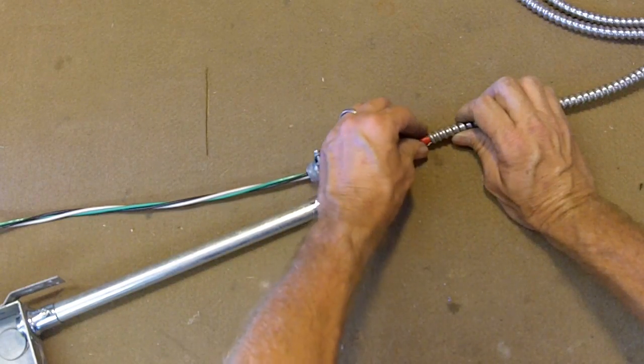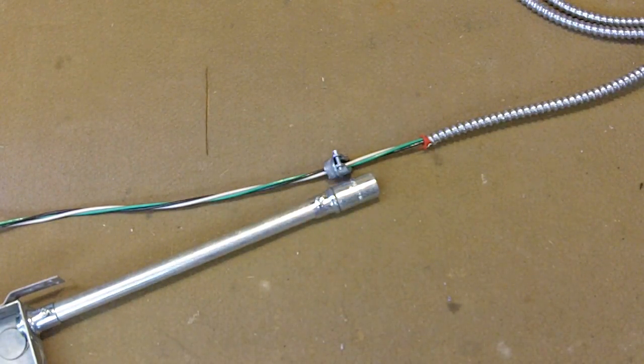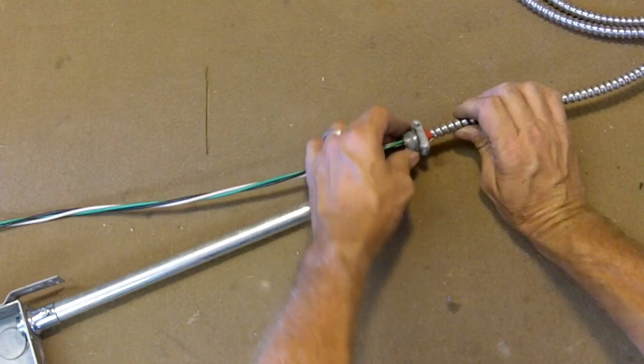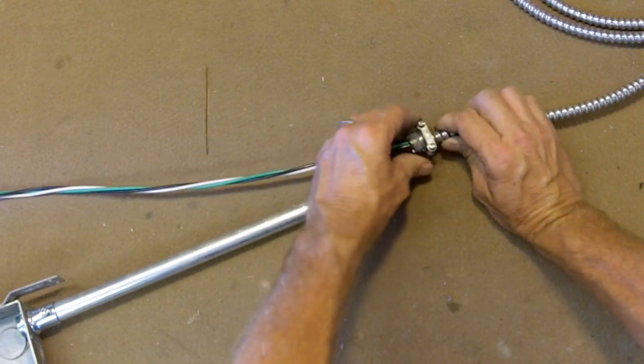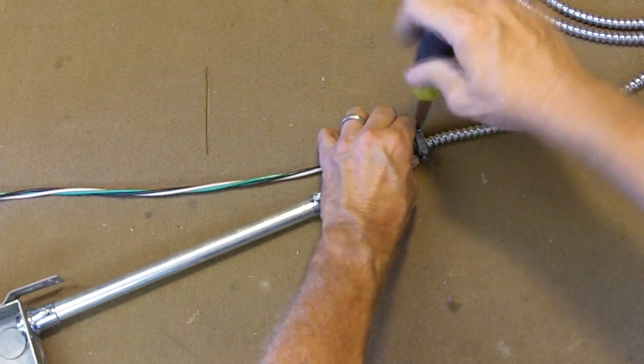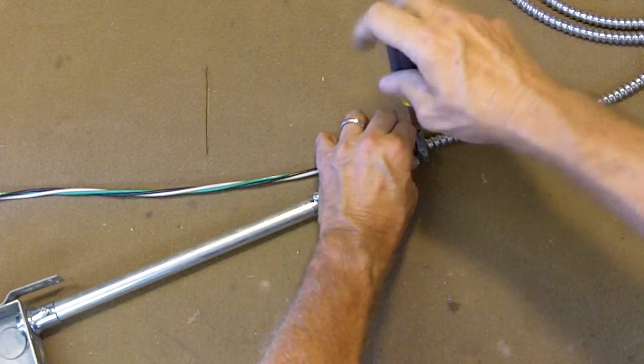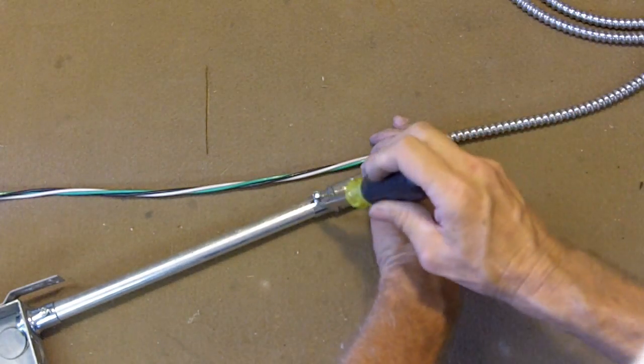But, just slide the MC connector over. Don't forget your anti-short. Notice how I turn the split the opposite direction. At least that's how I was taught. You guys might do it different. And then we'll slide that up. And we'll go ahead and tighten this up a little bit.